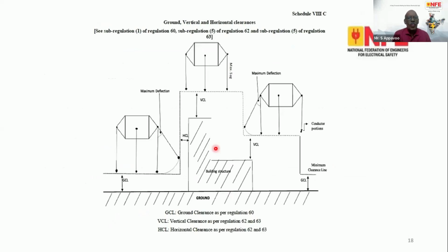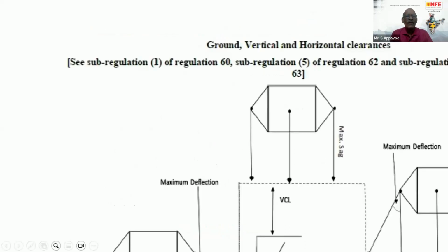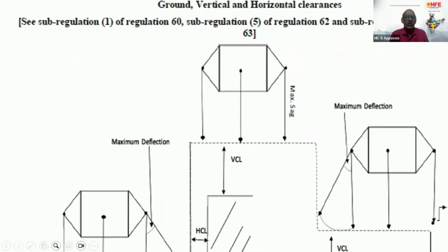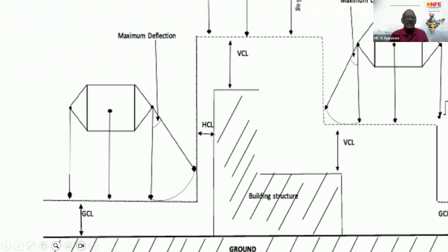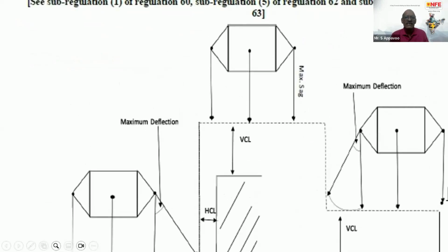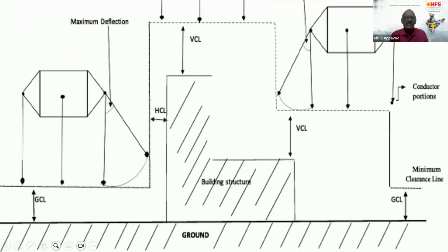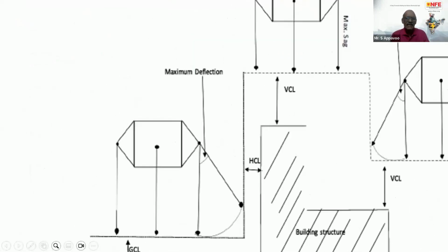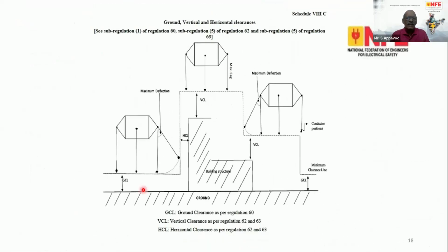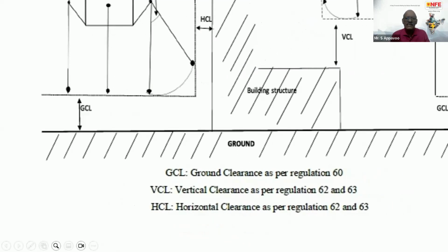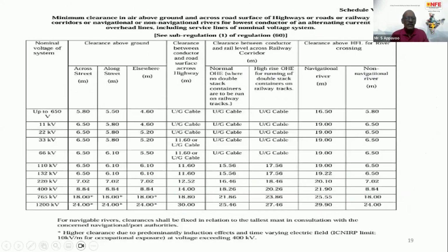So the supplier should also ensure the standard clearances, because I will magnify this. This is the vertical clearance and horizontal clearance for the overhead line, which should not affect the building. The horizontal clearance is based on the deflection, and the vertical clearance as well as the maximum deflection from the building structures. So the supplier has to lay the line according to these clearances. The standard clearances are also stipulated in the regulations. Regulations 62 and 63 provide the vertical clearance, and the horizontal clearance is as per regulation 62. So these are the provisions that should be observed by the supplier.